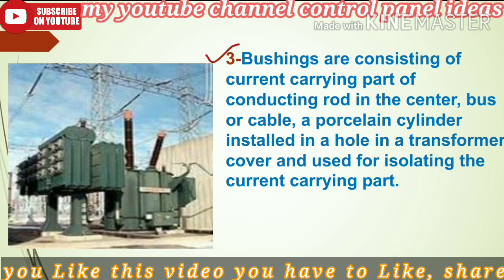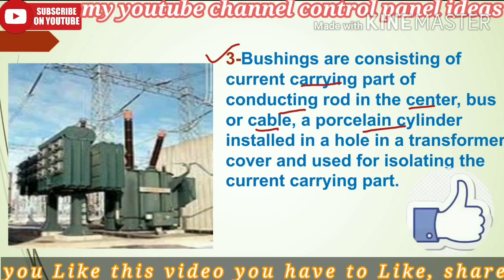Point 3, bushings consist of a current carrying part, a conducting rod in the center, bus or cable, and a porcelain cylinder installed in a hole in the transformer cover and used for isolating the current carrying parts.